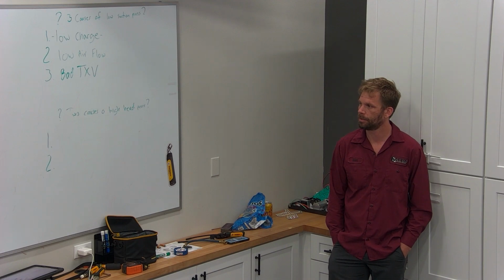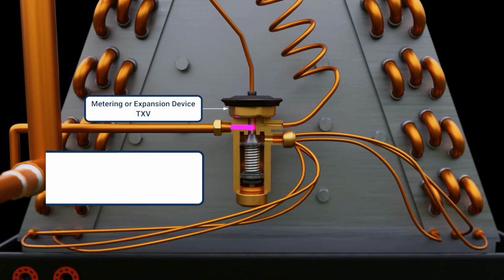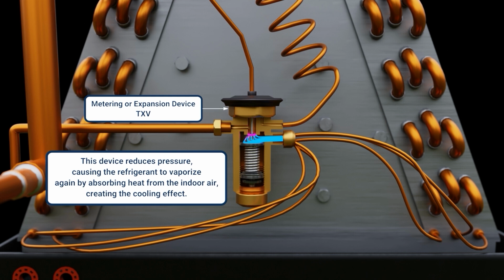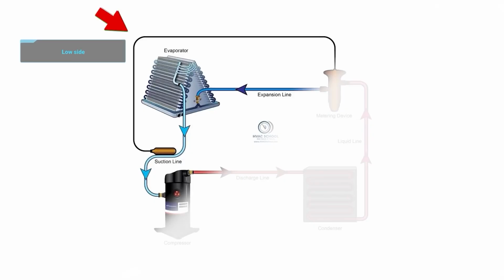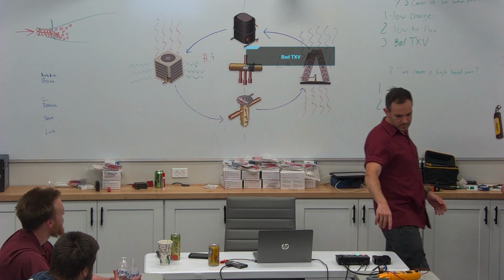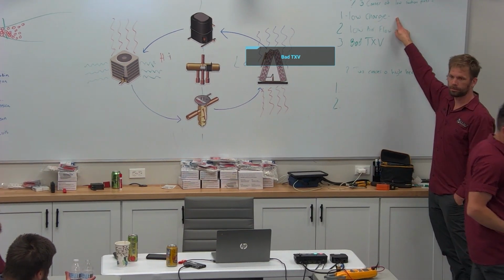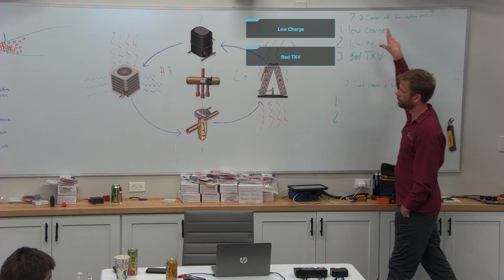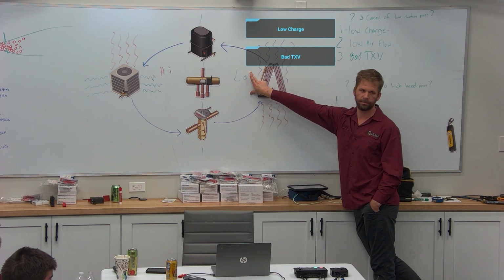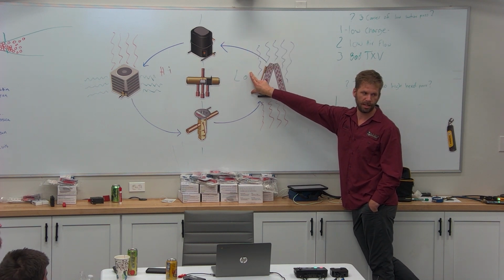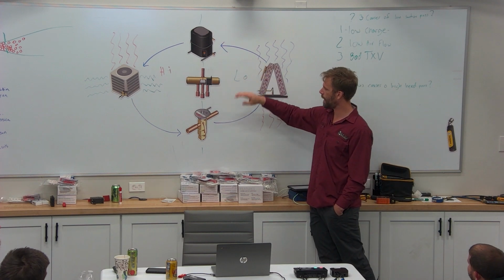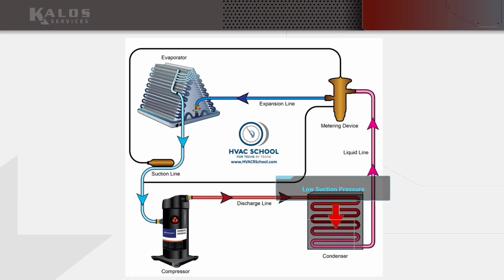A bad TXV, there's not as much going into the coil. That's right. It's not letting as much go into the coil. So if it's closing down, then our whole low side, which is being fed through this, is being fed less. A bad TXV and low charge look identical on your low side. Bad TXV and low charge both have low suction pressure.